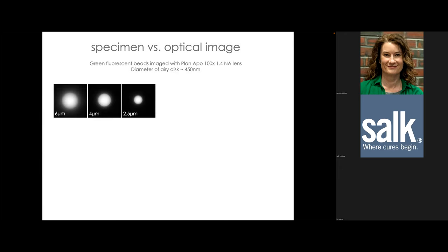This can be demonstrated with fluorescent beads. Here, beads of different sizes in the micron range — well above the resolution limit — are imaged with a high-NA lens whose Airy disc diameter is about 450 nm. Line scans across each bead show that the edges are blurred because every point source making up the microsphere is blurred by the PSF. We can see the size difference between a 2.5 µm and a 6 µm bead, and measurements using the full-width at half-maximum (FWHM) are quite accurate.